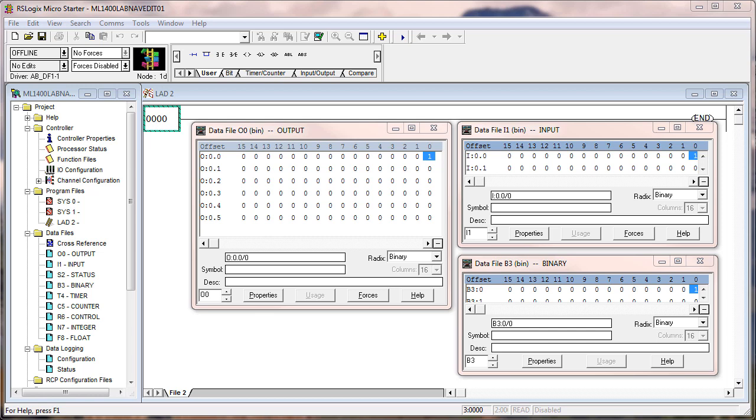The important thing here is for you to realize that if you download these 3 states to a controller, go in the run mode, and they get altered, they are now different in the controller than they are here in the offline data table that's in the RAM of your laptop or desktop. If you go offline, and we did not save, then you're going right back to the offline data table just the way it was when you left. If you had saved the online data table values, then input 00 right now would be off.